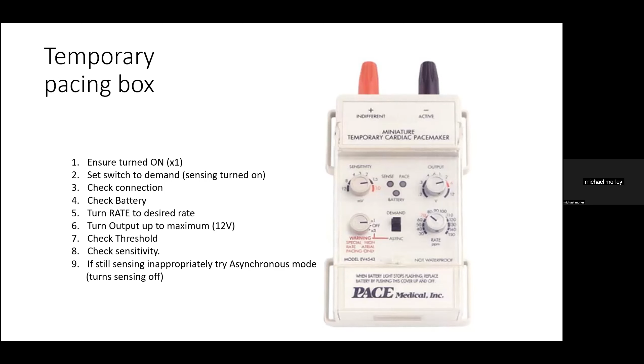And then what we need to do is we need to test the threshold. So we need to see how much energy we have to deliver down the lead in order to capture the ventricle and cause the heart to beat. So we'll start at a high output of 12 volts, and we can see that the pacing spike is followed by a QRS complex, and we're getting capture. We gradually lower the output by turning our output knob to the left. And eventually we get to a point where our pacing impulse is too small in terms of amplitude to capture the ventricle, and we see pacing spikes which are not followed by a QRS complex.